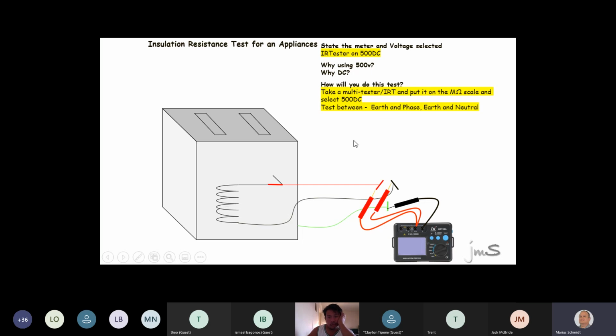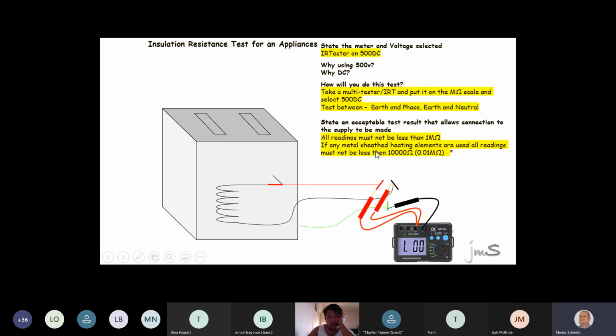And all your readings shall be greater than how many megohms? And if it's an appliance with an element in? 10,000. You guys happy with that? Now guys, my question is, do we call this a test on a non-live installation? It must be dead. If it's not dead, you can imagine what's going to happen with this lovely little insulation tester.